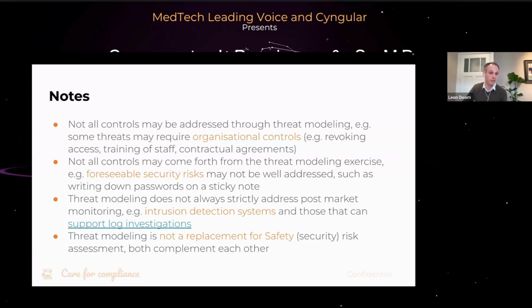Then the last part, and I've mentioned it already, is that it is not a replacement for safety risk assessment, right? They complement each other and they're intended to complement each other. And a risk on one hand for security could be a risk for safety on the other side. And sometimes, and that's also good to remember, they can complement each other, but they can also contradict each other. So in some cases, you might implement security controls which limit access to a medical device, whereas in certain safety alerts, you might want to get quick access to the medical device. But if there are a lot of layers of security around it, it might actually limit access to the device. So you should always balance safety against security, and that might be a bit challenging.